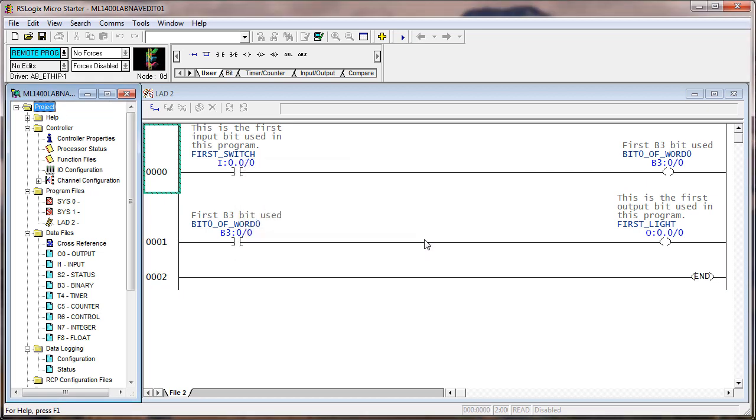Several ways to do that. It's okay to do it from here because it has nothing to do with the driver. You're already online. You're just switching between run and program. While watching the logic and the states of the memory locations that they address, toggle on the first switch on your field device simulator. So right there, you're looking, the switch is off. Toggle it on. Does anything happen?